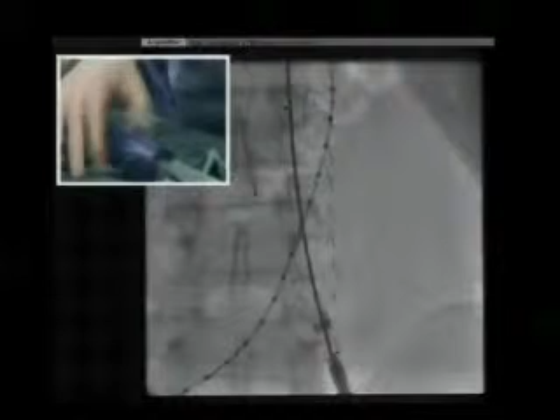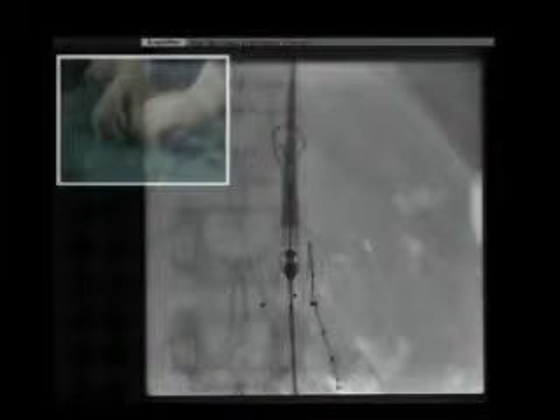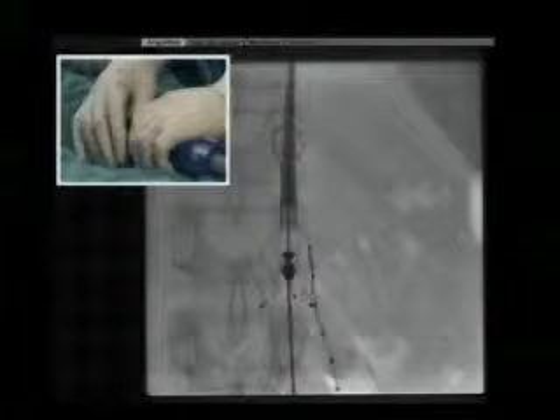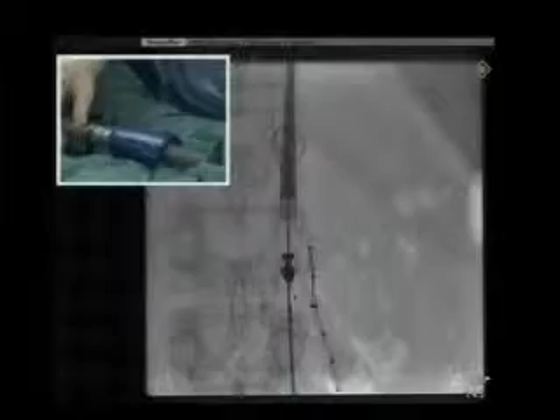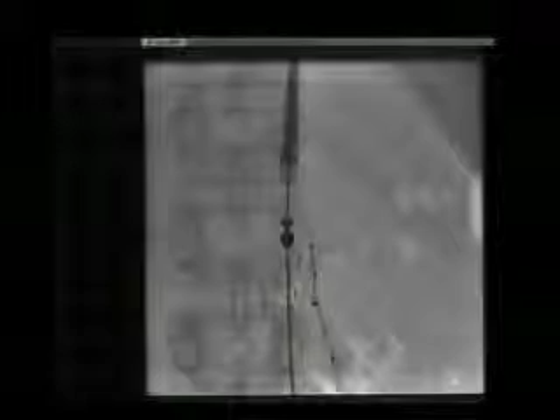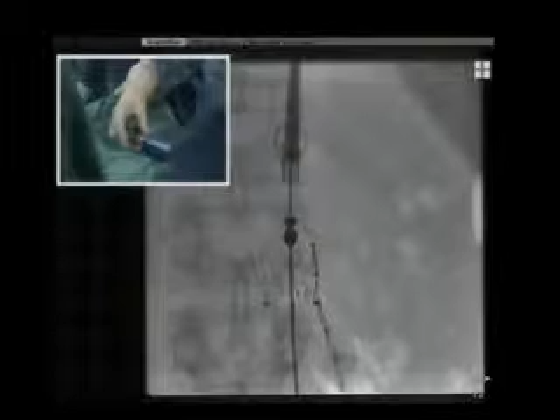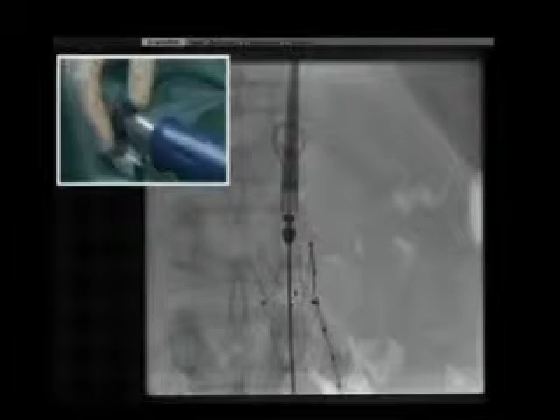And once we have released it, we are going to take care of the top cap and the nose cone. Now what we do is a clockwise movement of the lower wheel to open the top cap. Now the top cap is released properly. The bare springs are in the right position, and after this we push the device a little up and then do the opposite rotation of the lower wheel in an anti-clockwise direction. So this is going to recapture the nose cone, and we then slowly withdraw the assembly, making sure that it doesn't catch anywhere in the fabric.